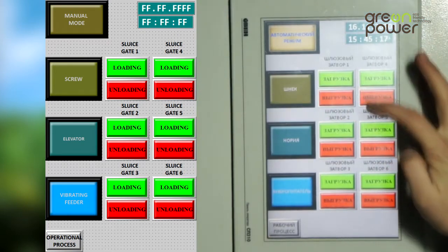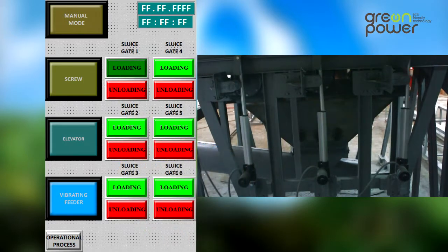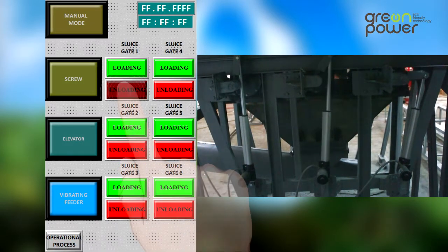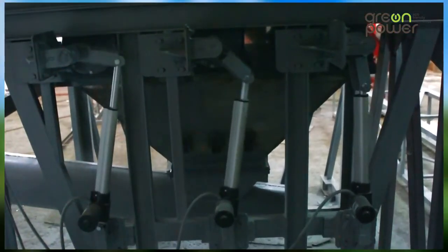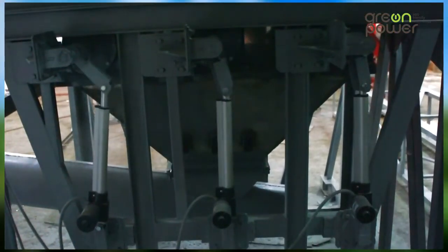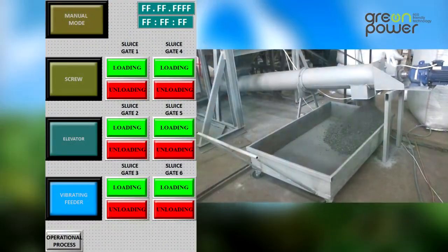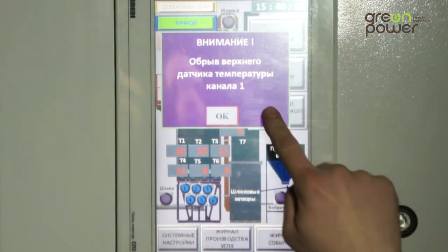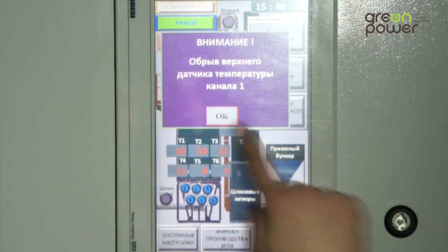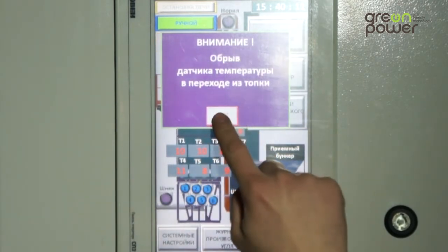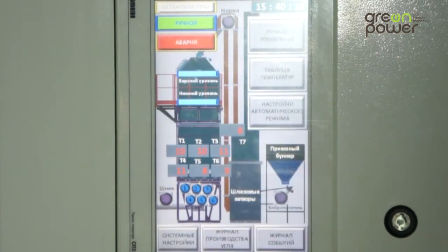There are buttons for activating each of the unloading devices. When unloading, the unloading device will be filled with charcoal and then discharged into the stabilization hopper below. When the stabilization hopper is filled, the auger turns on and the charcoal is discharged from the kiln. Pop-up windows provide notification to the operator of the automatic furnace control system and alert and warn the operator about necessary actions in relation to the operation of the kiln.